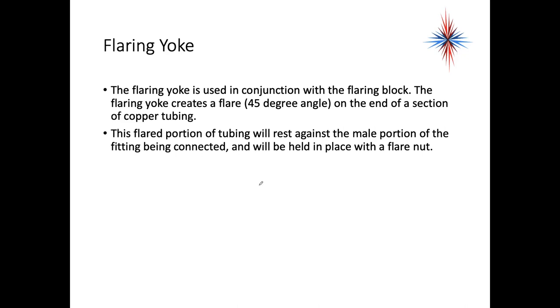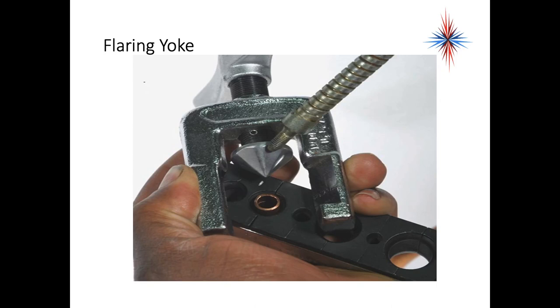The flaring yoke creates the flare, which is a 45 degree angle roughly at the end of a section of copper tubing. This flared portion of the tubing will rest against a male portion of the fitting being connected and it's held in place with the flare nut. This is the flare yoke. You see that the tubing sticking out of the flare block, and you see that the triangle side, the triangle wedge, is going to go down inside that pipe.